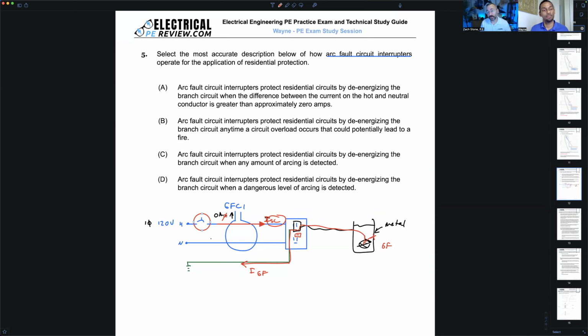Your GFCI is super sensitive as soon as it reads any current, right? When you have current coming in and current going out, just like you said, the differential is 0. As soon as you have current going out but not coming back in, and it no longer measures 0 amps, it's going to trip immediately.